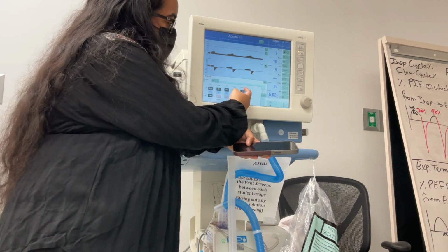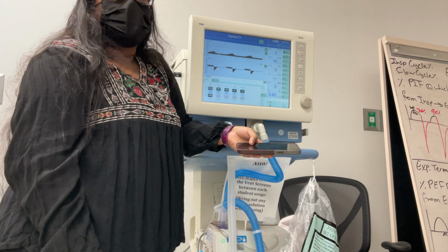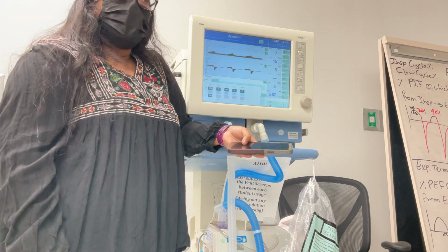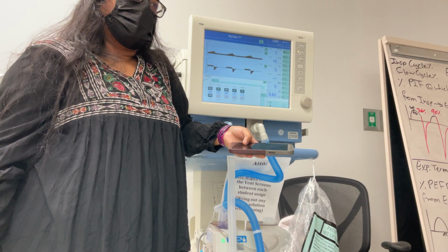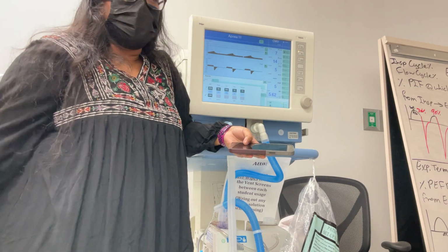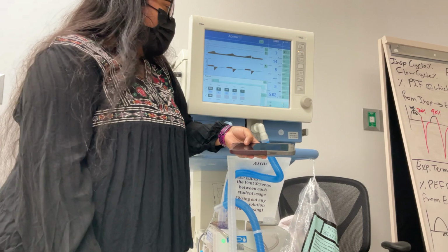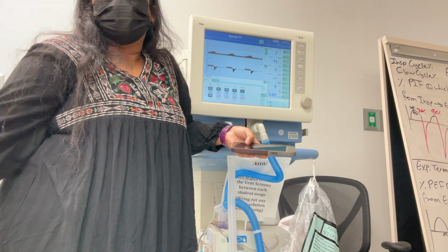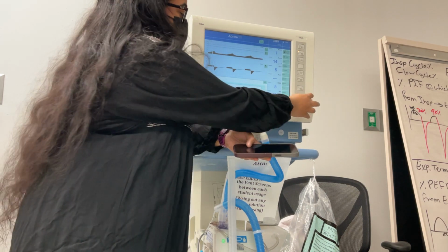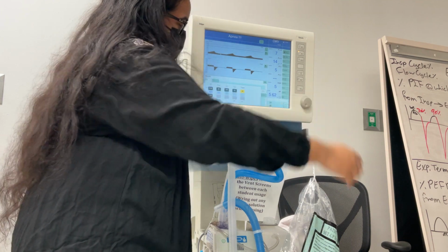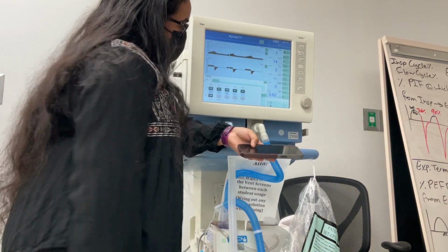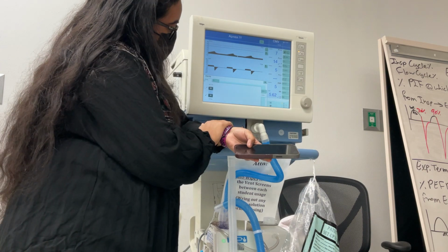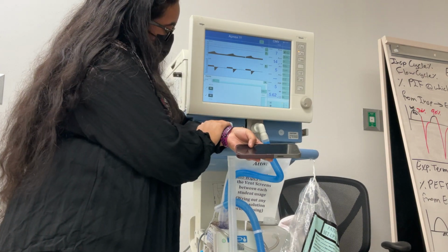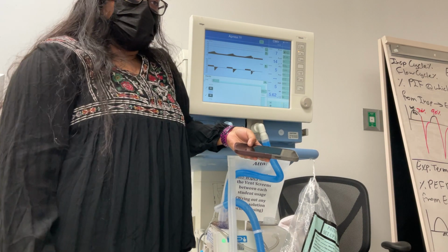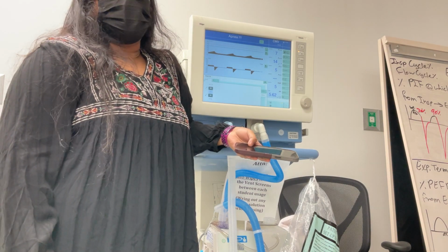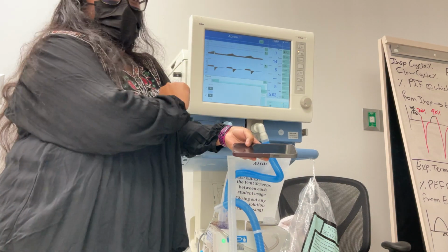And then apnea time, this is just T apnea. For adults, it's usually 20 seconds. Peds is like 15, and neonates is like 5 to 10. We don't want babies to go apneic. So adults is always going to be a standard 20. So we should probably change that. This one also has a limits page on the alarms. It's for end tidal CO2 monitoring. You won't have to know that for this checkoff, so ignore limits.